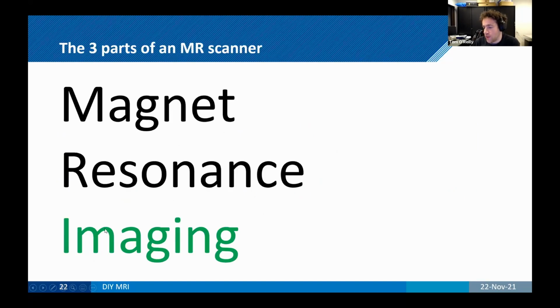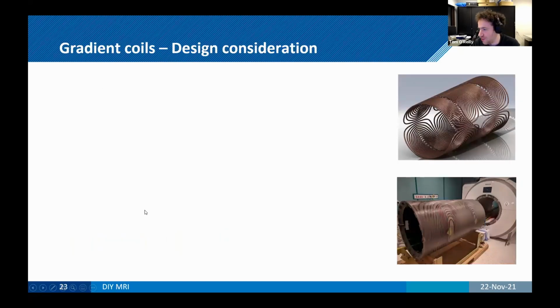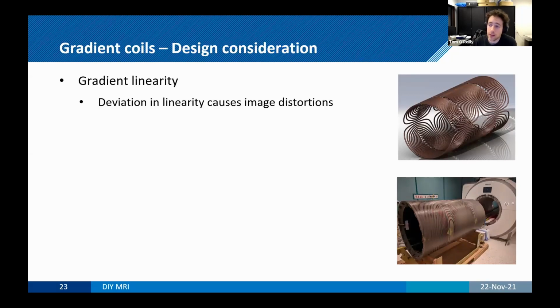I'll skip over the resonance for now, just because that's probably the most flexible part, and I think probably also where, maybe is it fair to say, that's where you guys have the most expertise as well. So I'll jump on that one last. So we'll start off with the gradient coils. So the gradient coils, there's a couple of design considerations that you have to make, and they're all trade-offs. So you can't have perfect for all of them. So this is a balancing act that you'll have to do, also depending on the electronics that you have and the system size and things like that.